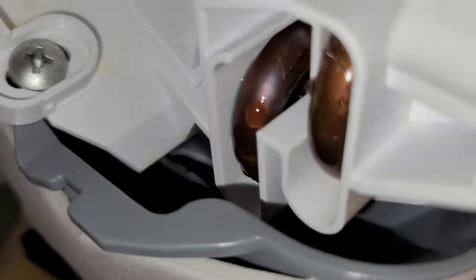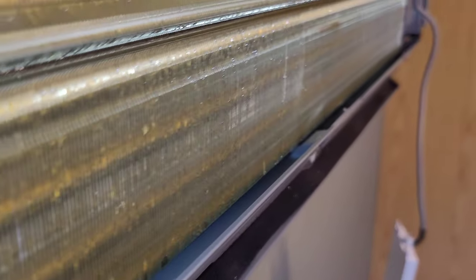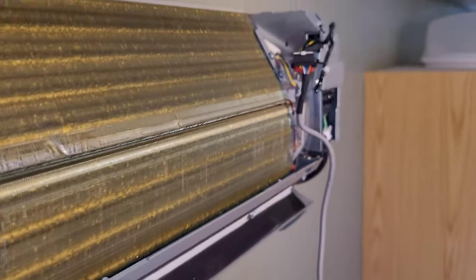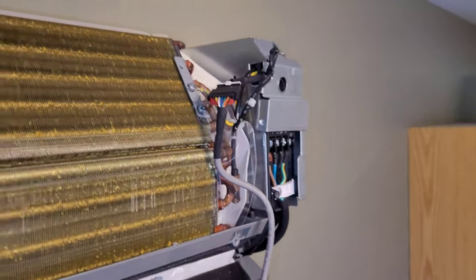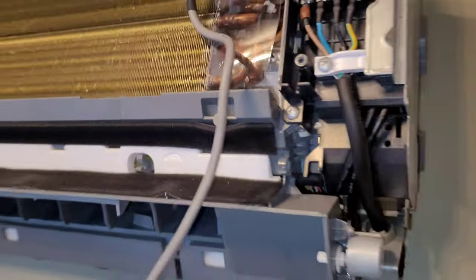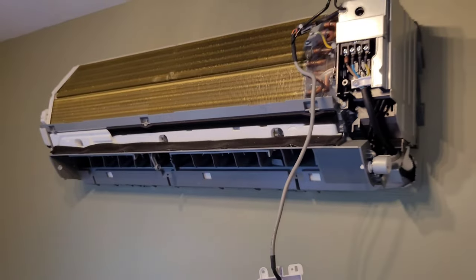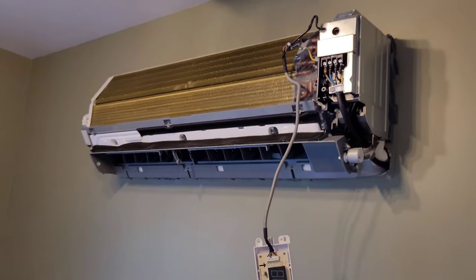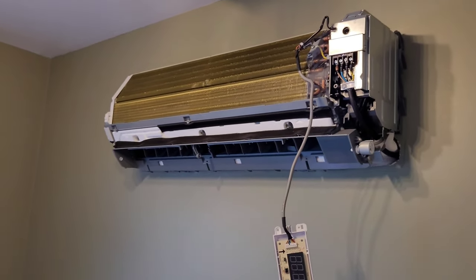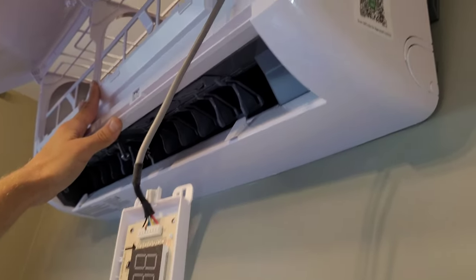So depending on what side you hooked your drain to, this is where my drain actually exits the pan into the line. So it's a good idea to dump a bit of vinegar down here, maybe some hot water. You could also use some pan and drain treatment from a company like NuCalgon or Viper. I'll put links to all that below. Once you've done the drain line, the blower wheel, and the coil, you're pretty much done. So I'm going to show you how to get it back together and we'll fire it back up.